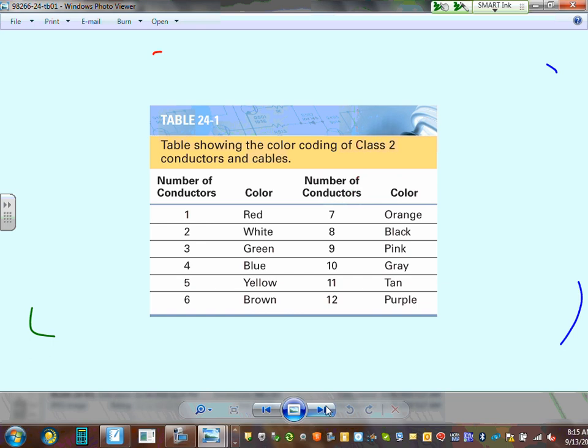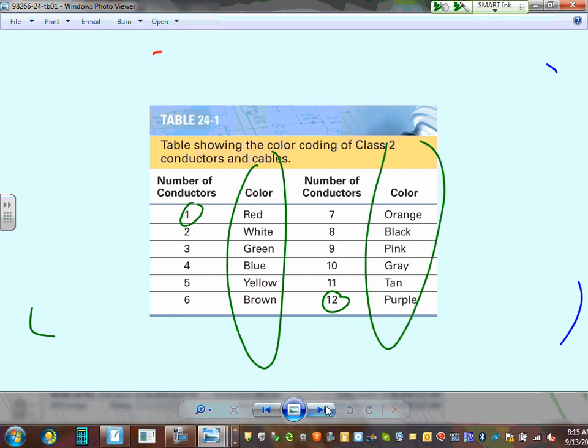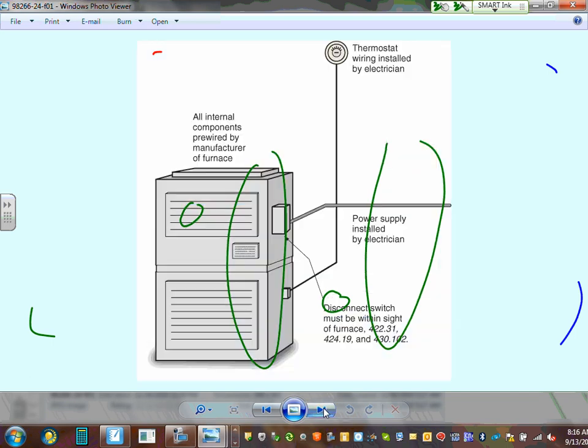For Class 2 circuit color coding, thermostat wire comes in up to 12 conductors: conductor 1 is red, conductor 2 is white, all the way to conductor 12 which is purple. This color coding helps you identify which wire lands on which terminal, based on the manufacturer's wiring diagram. When you wire the control circuit for a furnace, all these wires land on specific terminals inside the controller. Color code is a big deal for the control system.